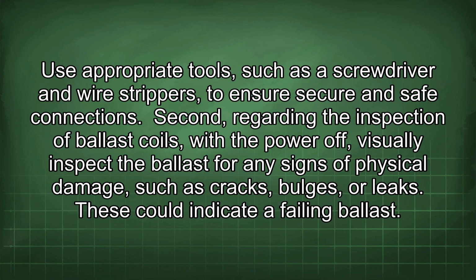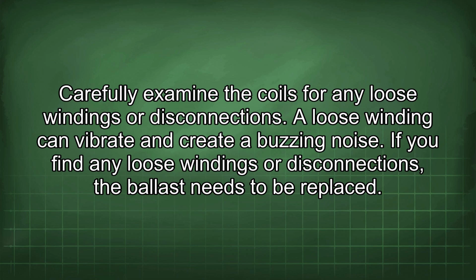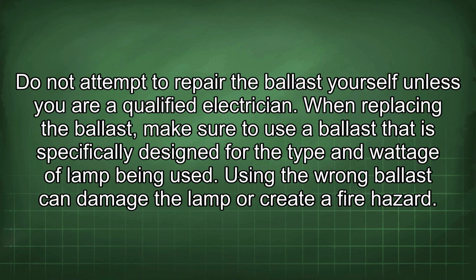Second, regarding the inspection of ballast coils, with the power off, visually inspect the ballast for any signs of physical damage, such as cracks, bulges, or leaks. These could indicate a failing ballast. Carefully examine the coils for any loose windings or disconnections. A loose winding can vibrate and create a buzzing noise. If you find any loose windings or disconnections, the ballast needs to be replaced. Do not attempt to repair the ballast yourself unless you are a qualified electrician. When replacing the ballast, make sure to use a ballast that is specifically designed for the type and wattage of lamp being used. Using the wrong ballast can damage the lamp or create a fire hazard.